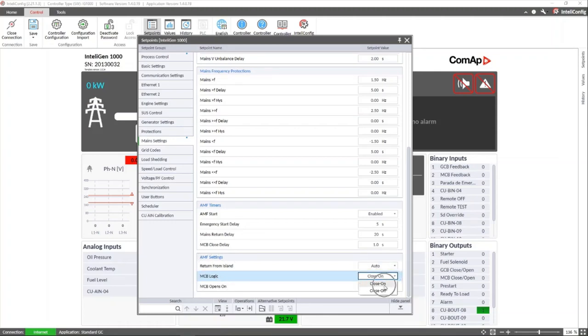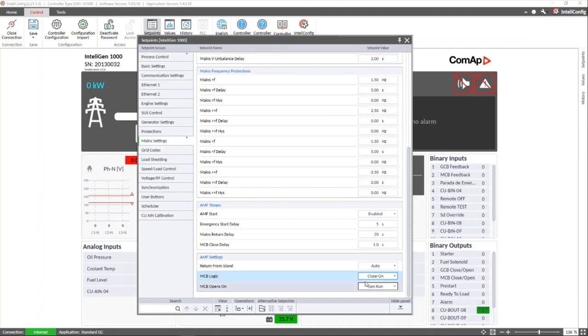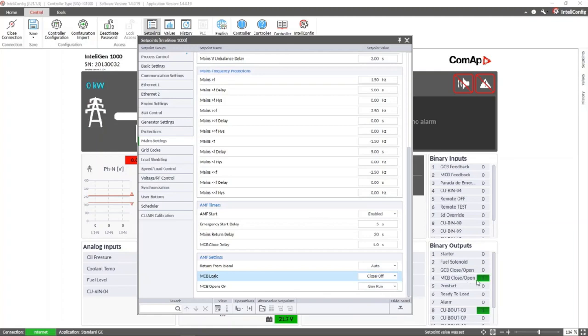The configuration of this parameter can be 'closed on' to configure the direct logic, where to close the MCB we will be activating the output and to open the MCB breaker we will be deactivating it. Or we can choose 'close off' where the reverse logic will be active, which means to close the MCB we will be deactivating the output and to open the MCB the output will be active, as seen on the screen.